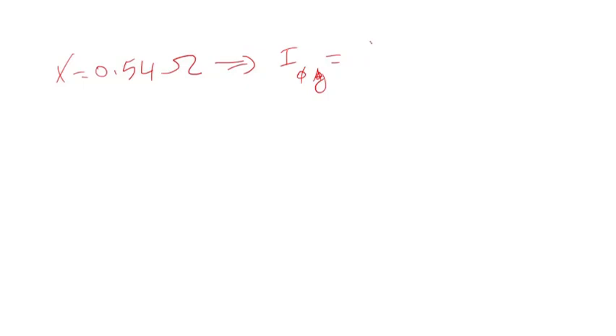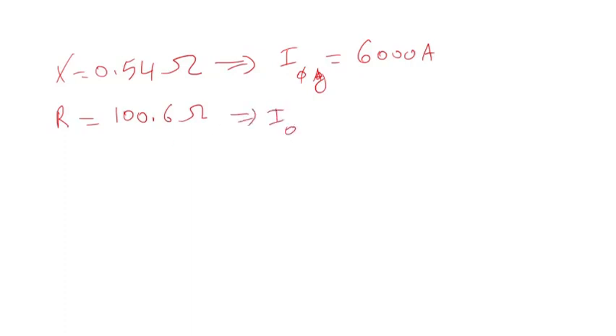Option two was to add a neutral grounded resistor, and we calculated the required resistor to be 100.6 ohms in order to limit the phase-to-ground fault current to 6,000 amps. So you can see, to get the same results, the reactor value versus the resistor value are quite different.